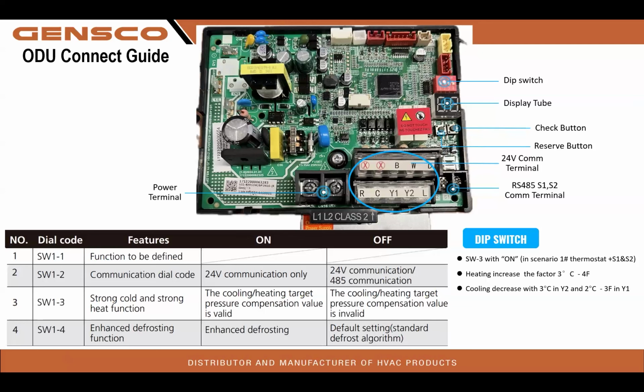Dip switch and dial code functions. S1-1 is to be defined. S1-2, communication dial code, 24-volt communication only. SW1-3, strong cold and strong heat function. The heating, cooling, target pressure compensation value is valid. Always refer to your installation manual for your dip switch functions.